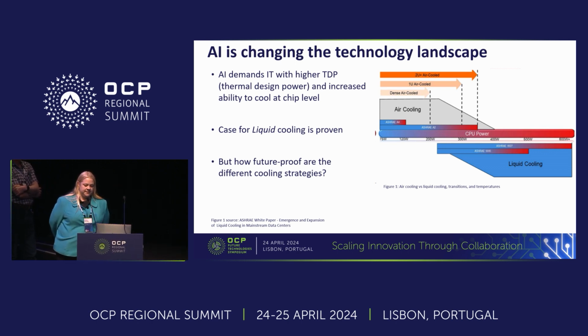2023 was really an inflection point where the advent of generative AI dramatically shifted the technology landscape, and now the entire industry is focused on how to support AI. AI requires IT components with significantly higher thermal design power, and with that comes the increased need to cool at the chip level. Figure 1 illustrates the limits of air cooling and where the case for liquid becomes required. Based on data from ASHRAE, air cooling really starts to max out at around 350 watts at the chip level. In fact, Intel's current generation CPU is at that 350 watt level today. NVIDIA's next-gen GPUs are projected to be near the 1 kilowatt mark and beyond, where liquid cooling will be required.